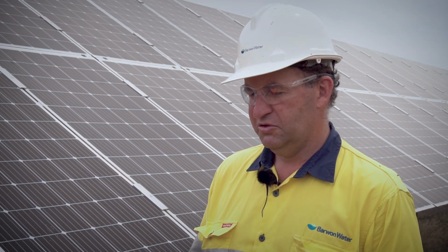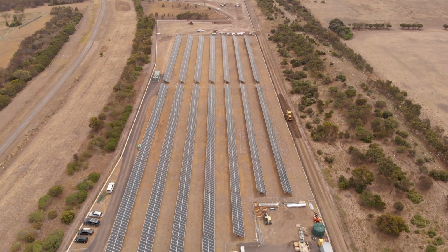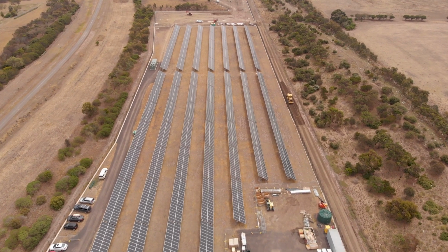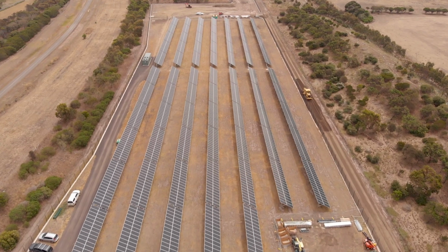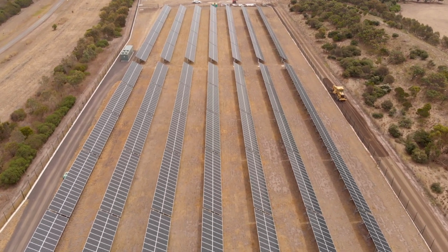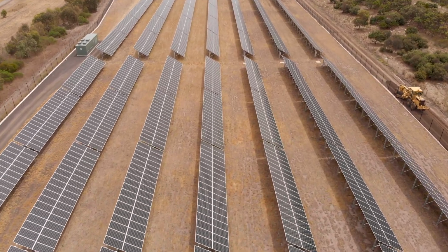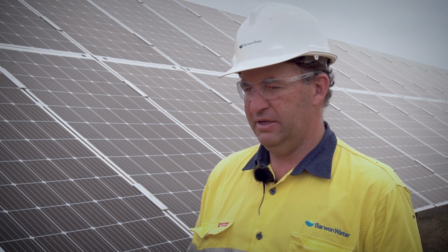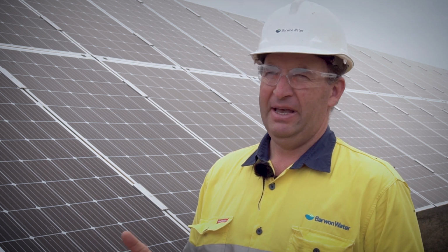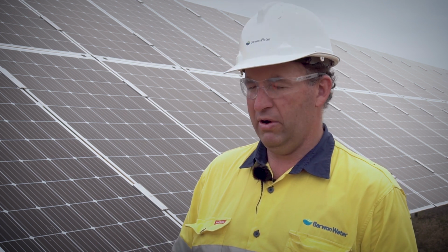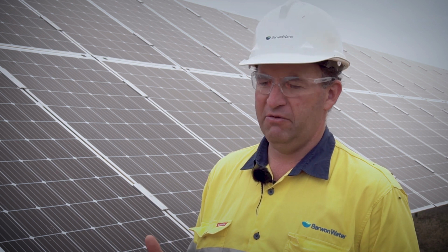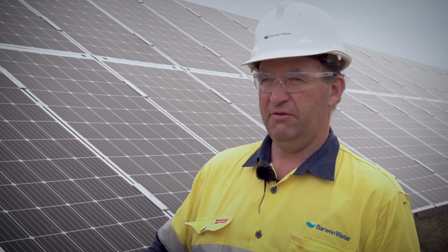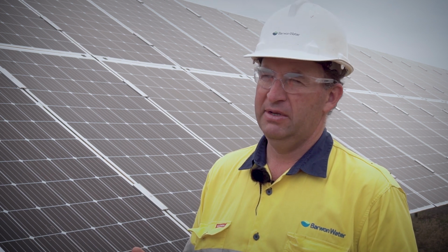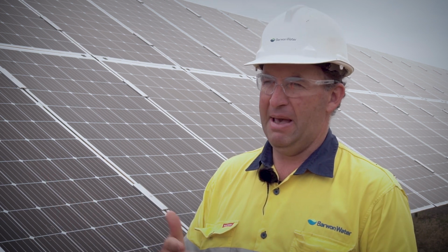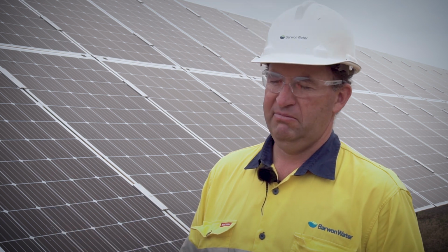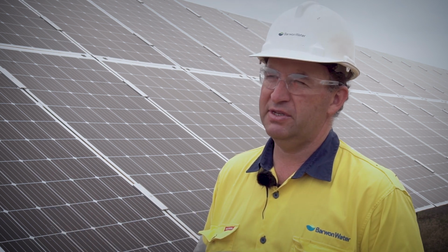So we got 1 megawatt, 2,844 panels, roughly 1.46 kilometres in string length of panels themselves. And that's based off seven arrays deep. So you can modulate that, and the important part is your string design as to how you want to wire them in a series, but also from a maintenance perspective, it's important that if you need to come out and find if you've got a string failure, how the electricians can then map that you're on string S1 of rack 6 or something, or inverter 6.